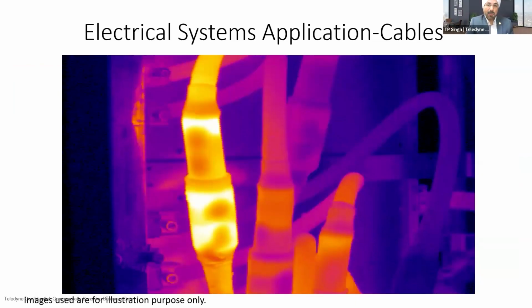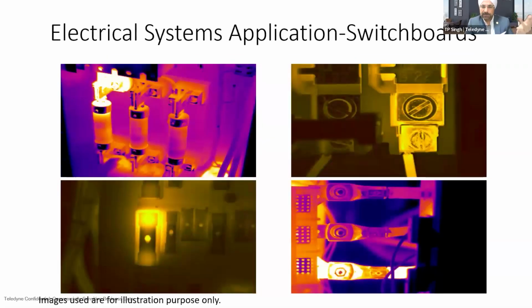Similarly, joints and terminations are a very critical component of the entire network. Again, with one snap you will be able to see whether some connector is having a problem or not. In this image, you can see the R, Y, B phases - only one joint has got the problem. If the current in all three is the same, that means one connector definitely is having an issue. So again, without touching anything, without taking a shutdown, from a safe distance, you will be able to see all these things. Similarly, if you have switchboards or fuses with a major issue, with one snap you will be able to see that.